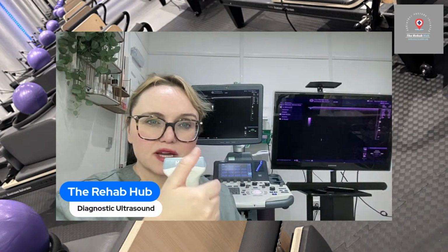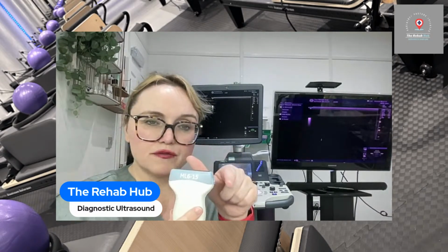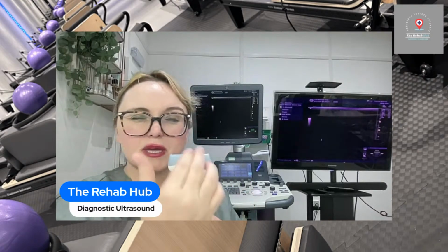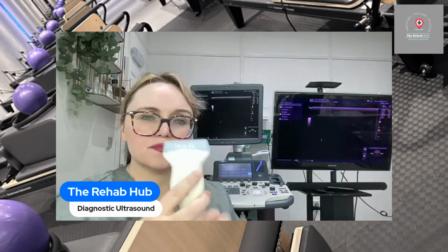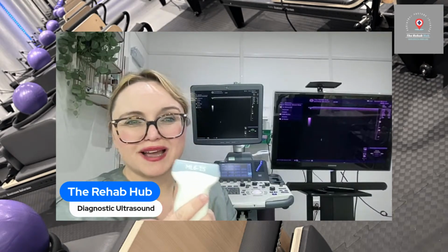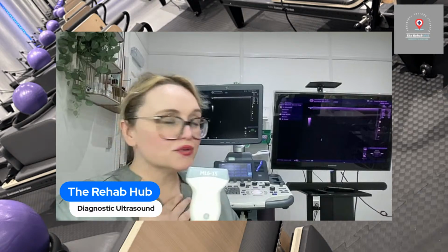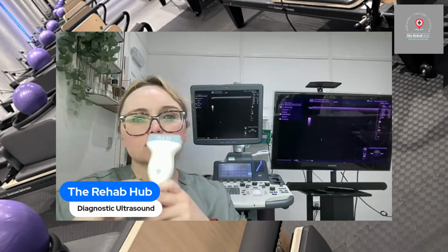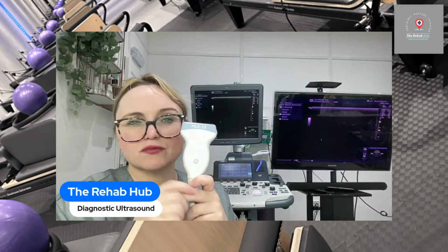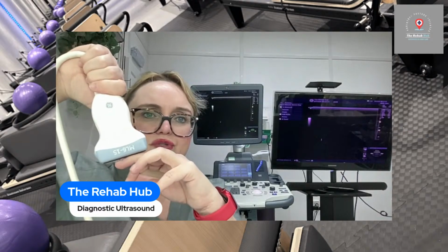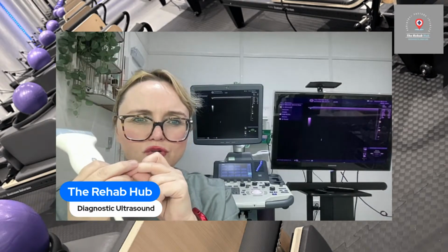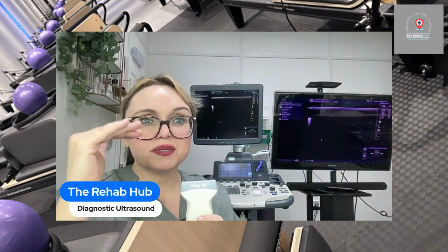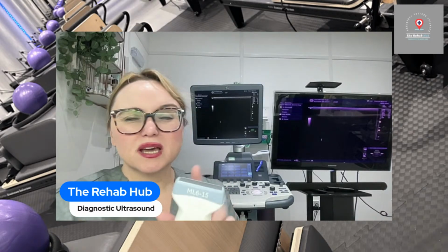So the transducer for a sonographer scanning fetuses would be what's called a curvier probe, and it would be looking somewhere around maybe 4, 3, 2 frequency, whereas the lowest this one goes to is 6. So it's still quite superficial because it goes as high as 15. Pretty superficial structures. I don't have it here, but you can also get the little hockey stick probes, for looking at some of the phalanxes, some really small structures. I just really like this one. If I was wanting to do fingers and toes, and look at really small structures, then I'd want a higher frequency, and I think they go up to 18. This one goes to 15.